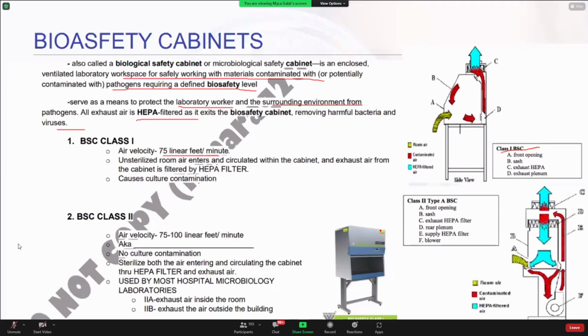It allows unsterilized room air to pass into the cabinet, as shown by the yellow arrow, and circulate around the area and materials within the cabinet. This sterilizes only the air being exhausted, but does not sterilize the air coming in. In the figure, room air flows into the cabinet and is circulated out through the HEPA filter, or high efficiency particulate air filter, and the exhaust portal.